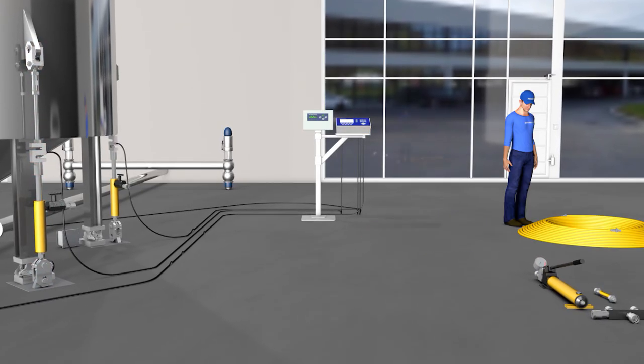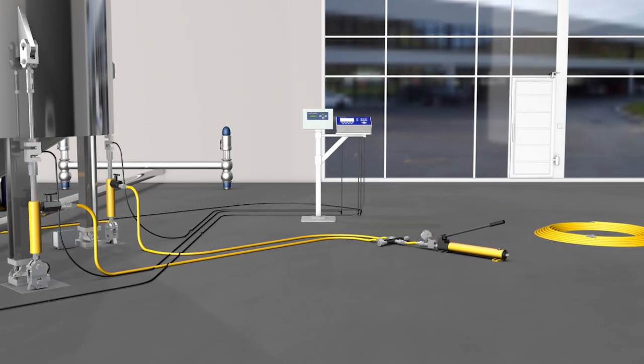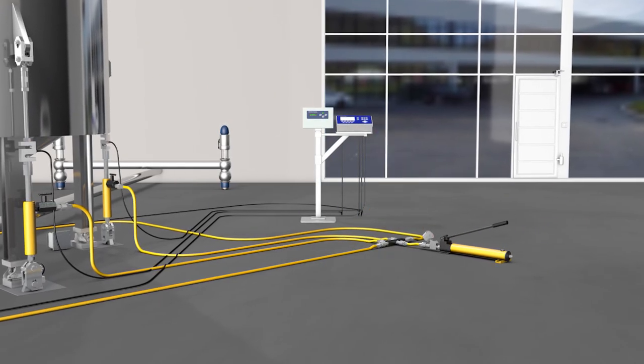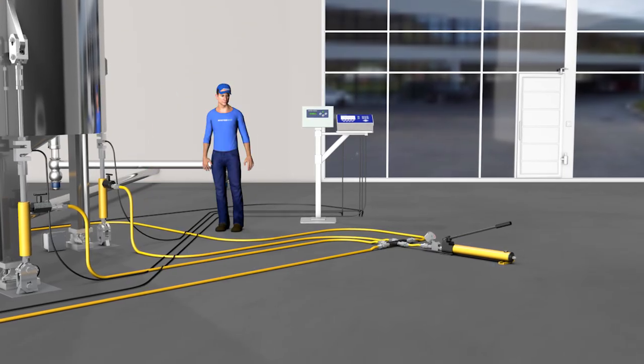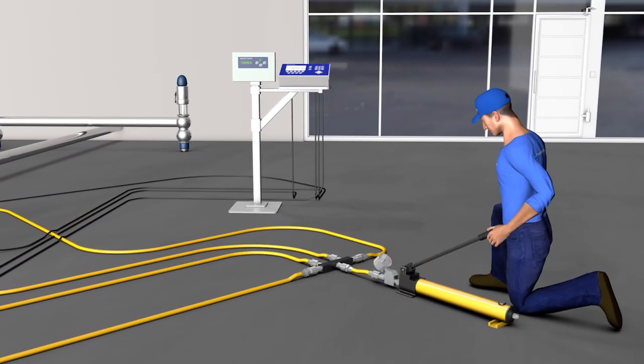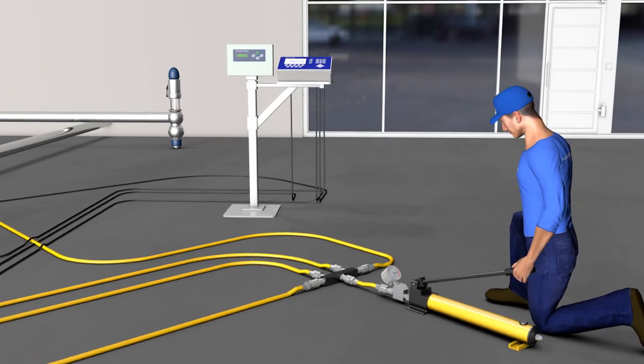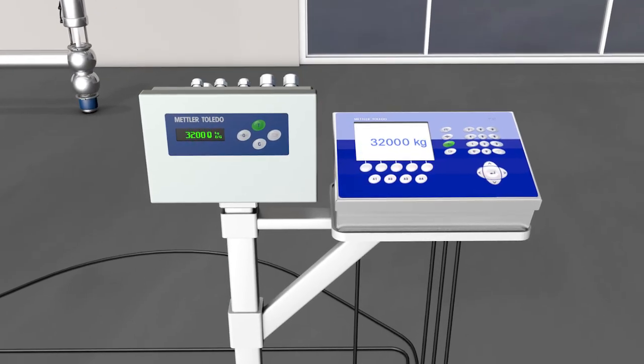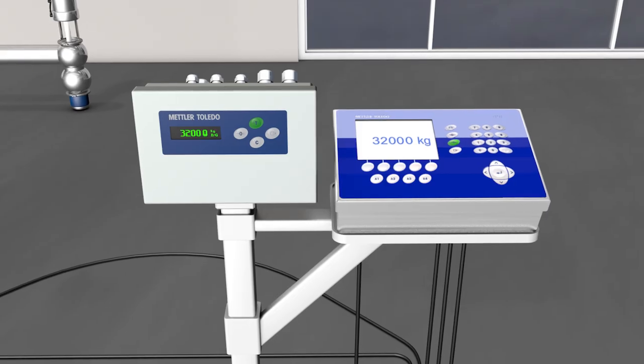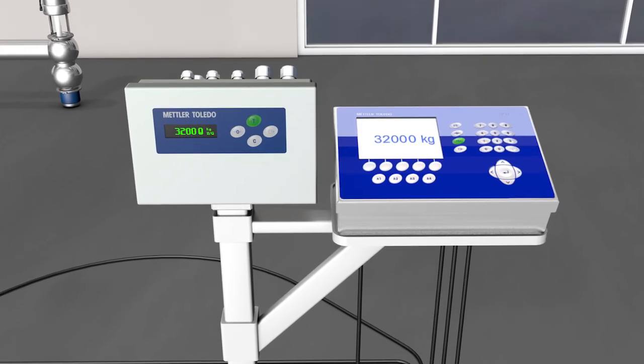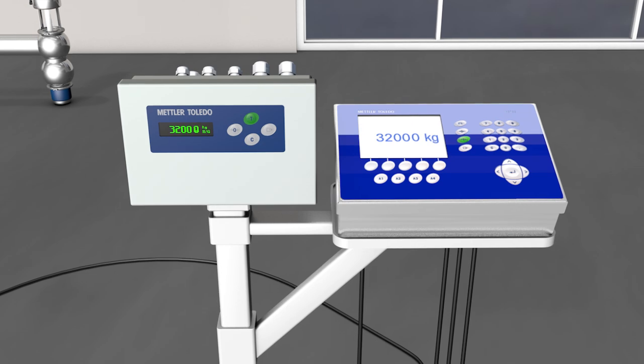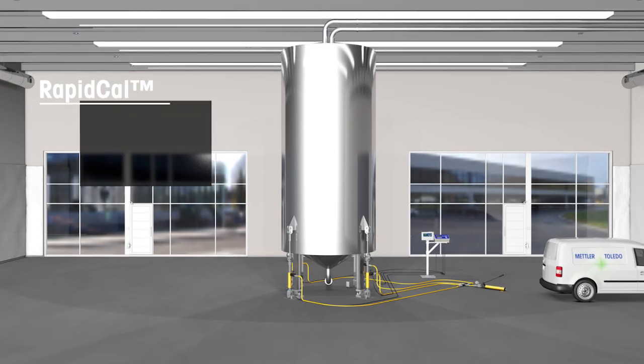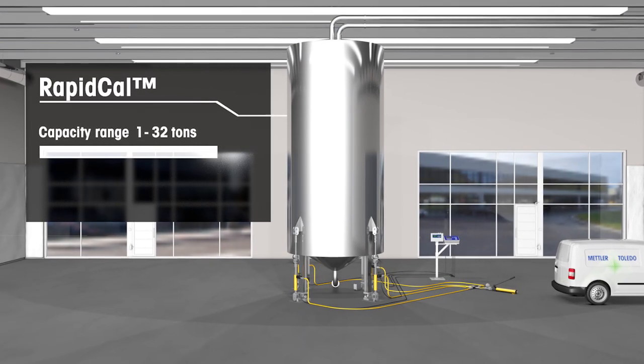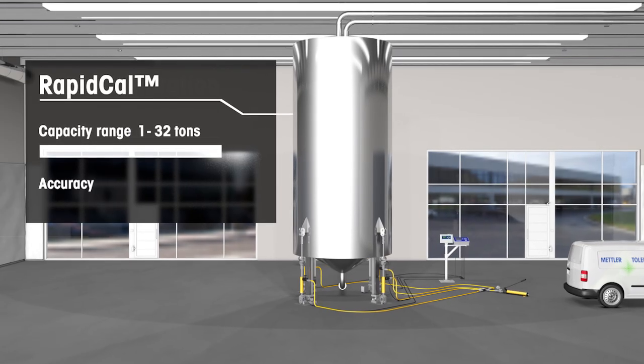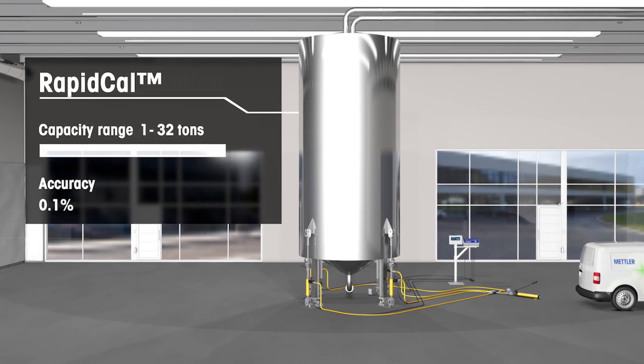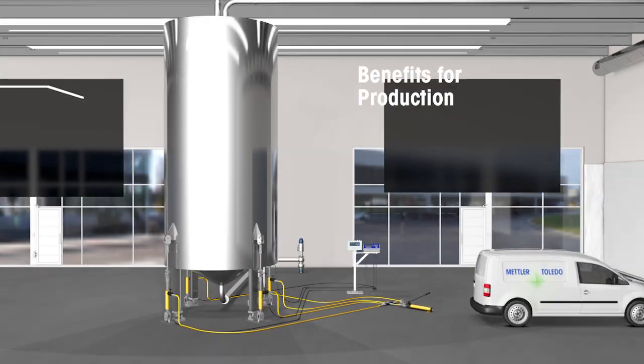After that, the hydraulic components, such as cylinder, hoses, manifold, and hand pump, are connected. By increasing the hydraulic pressure, force is applied, which is monitored by reference load cells. The calibration terminal values are compared to the tank scale terminal. Our experts do the calibration quickly and efficiently for you. The RapidCal Tank Scale Calibration method can be used in the 1 to 32 ton capacity range. The equipment used in this method can achieve 0.1% accuracy.